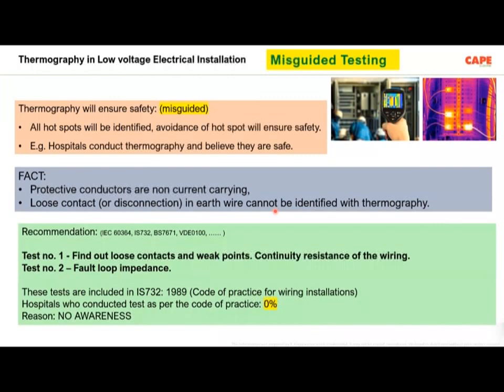And if you really want to find loose contacts, you should do the test called continuity resistance of the wiring, which is test number 1 in the sequence of 10 tests recommended in IS732. The second test which I would recommend is the fault loop impedance test, which is the 6th test in the sequence of the IS732. These tests are included in IS732 1989, Code of Practice of Electrical Wiring, 1989.